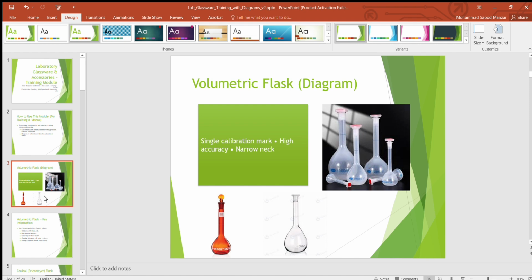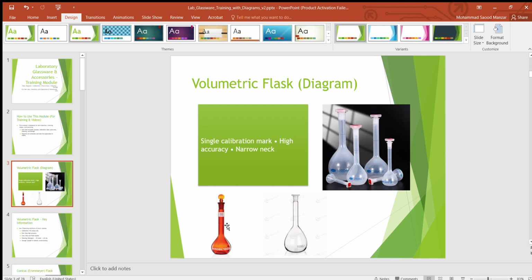This has a single calibration mark, the mark up to which we have to pour our liquid. This one is made of a special plastic. Usually these are colored glass, which does not allow light to pass, so it can be used for storage of organics. It is chemically inert to most organic solvents, so there is no chance of leaching, no swelling, no deformation, and it is safe for hexane, acetone, ethanol, methanol, toluene, chloroform short term, dichloromethane short term.